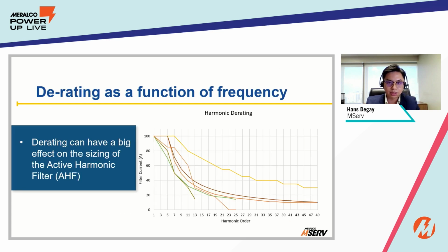It should be noted that not all harmonic filters are equal. When selecting a harmonic filter, there is a need to know the derating factor because it can dictate that the selected equipment is actually insufficient or undersized to mitigate the harmonic systems. In this graph, it can be seen that some harmonic filters can drop off on the 7th harmonic, which is one of the most common harmonics in the field, due to 6-pulse rectifiers, VFDs, and the like.